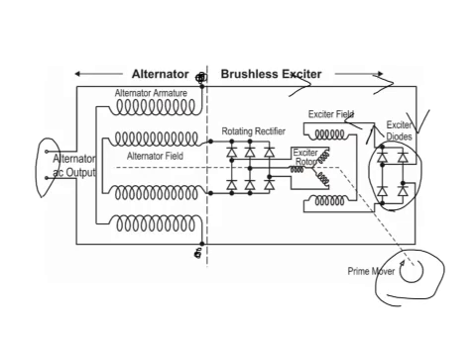In order to start building up a voltage at our output, there first had to be residual magnetism — a small, fairly weak north and south pole — existing on the exciter field. If there is no residual magnetism, we may not build up voltage at all. We're assuming here that we do have some residual magnetism in that north and south pole in the exciter field, which is located in the stator. The exciter is not a big part of the machine — it's really just the bell end of it. We're not passing much current through the exciter field; it has low current but many turns of small wire to produce a strong enough electromagnet to excite our rotor.